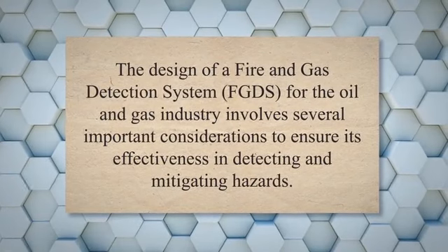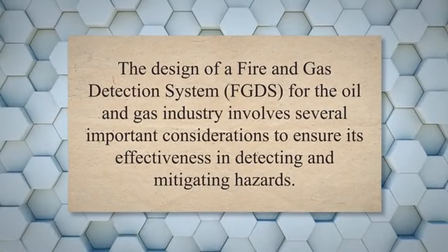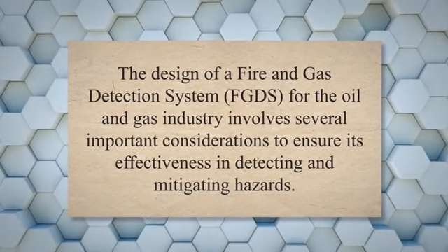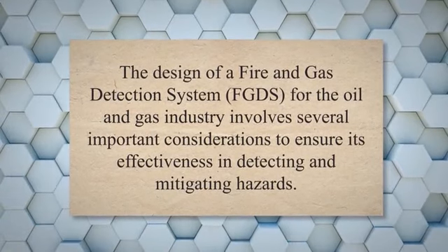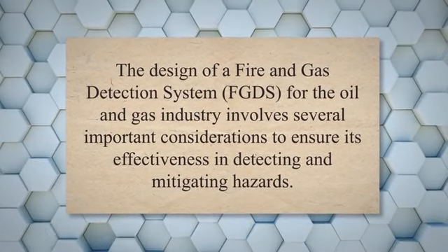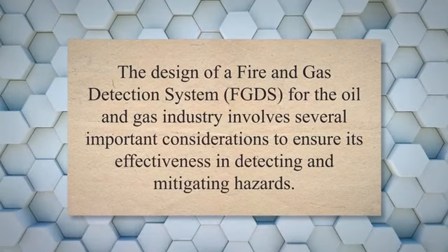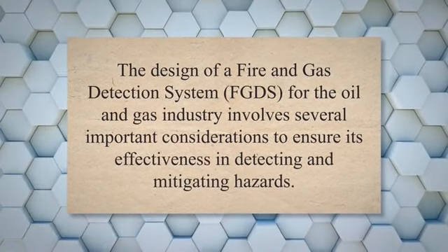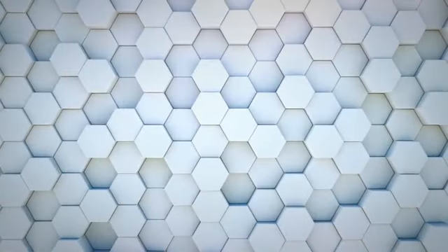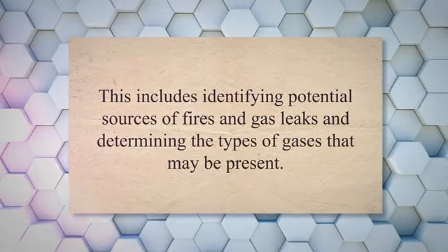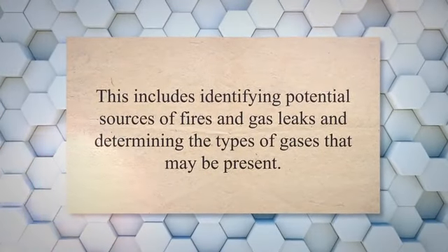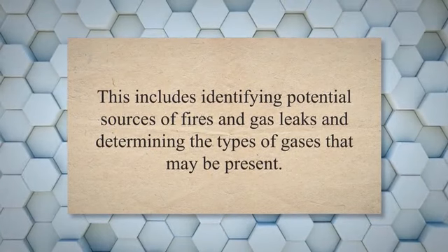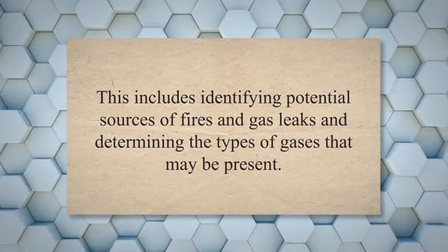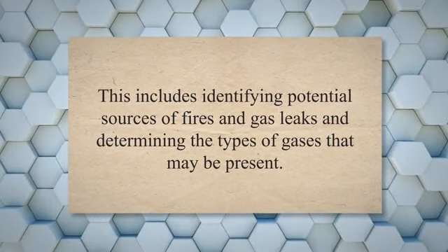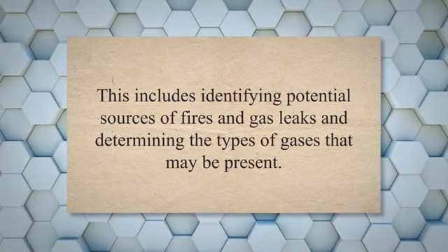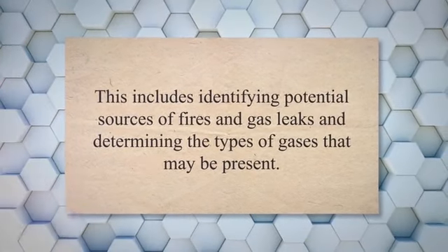The design of a fire and gas detection system, FGDS, for the oil and gas industry involves several important considerations to ensure its effectiveness in detecting and mitigating hazards. Here are some key design considerations. Hazard identification. The first step in designing an FGDS is to identify the potential hazards in the facility. This includes identifying potential sources of fires and gas leaks and determining the types of gases that may be present.